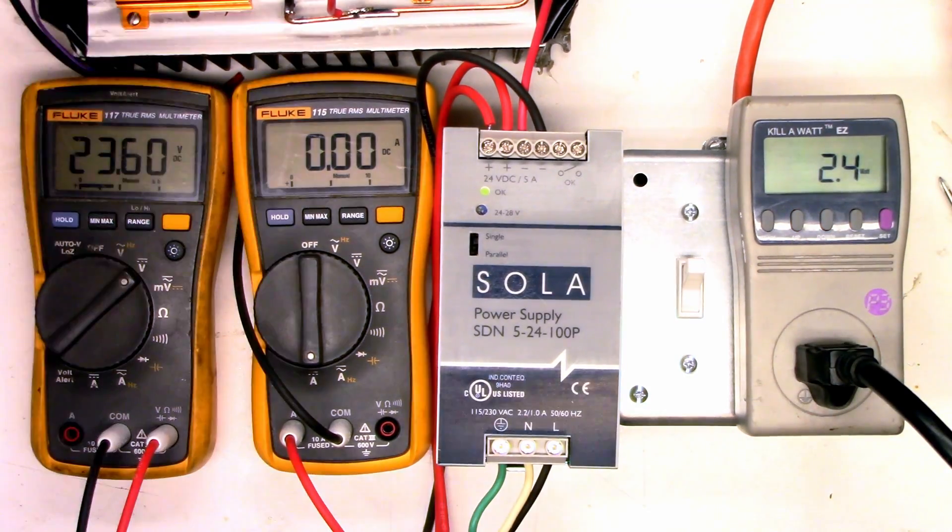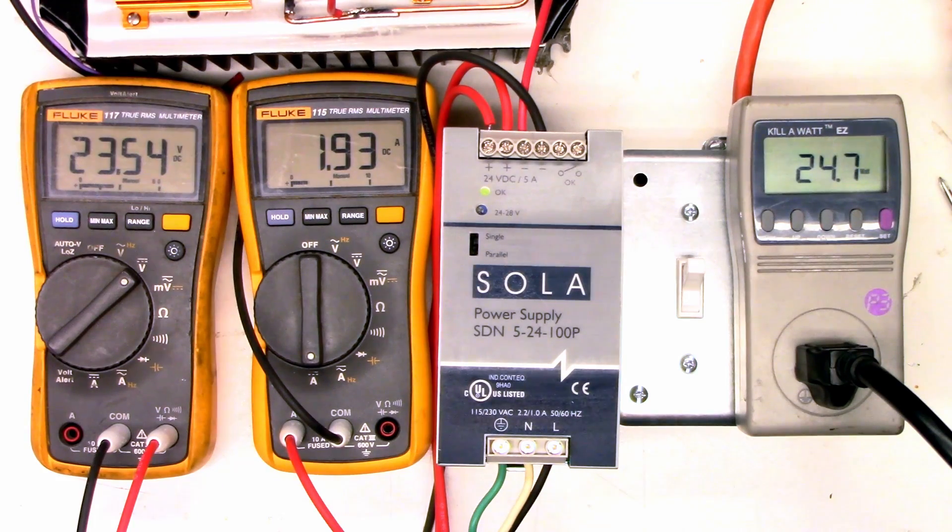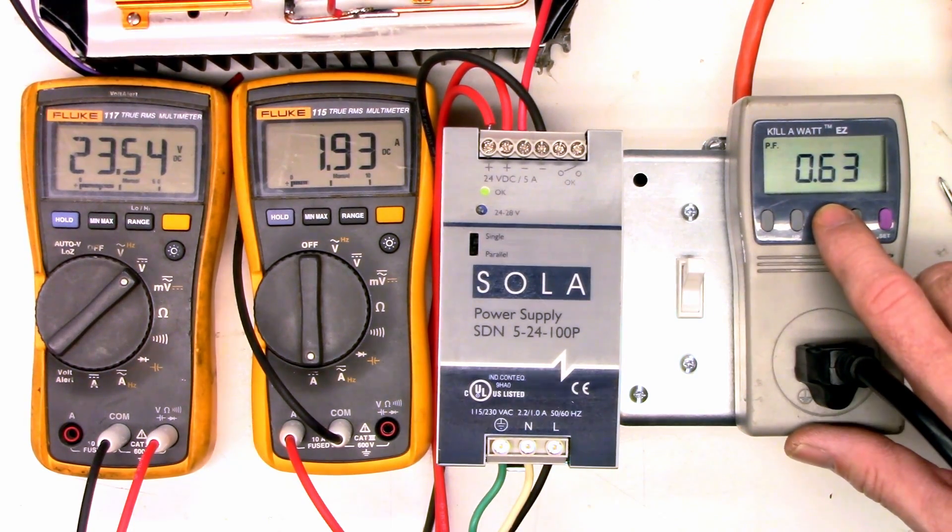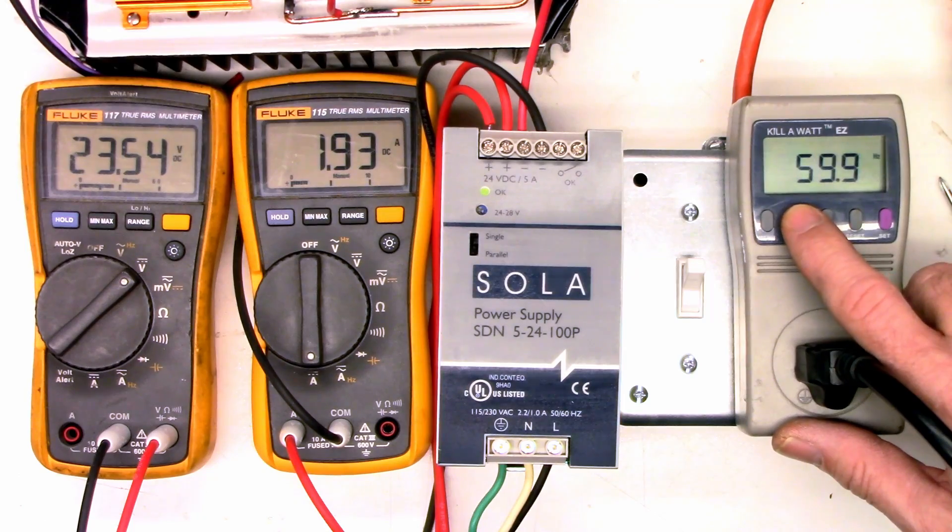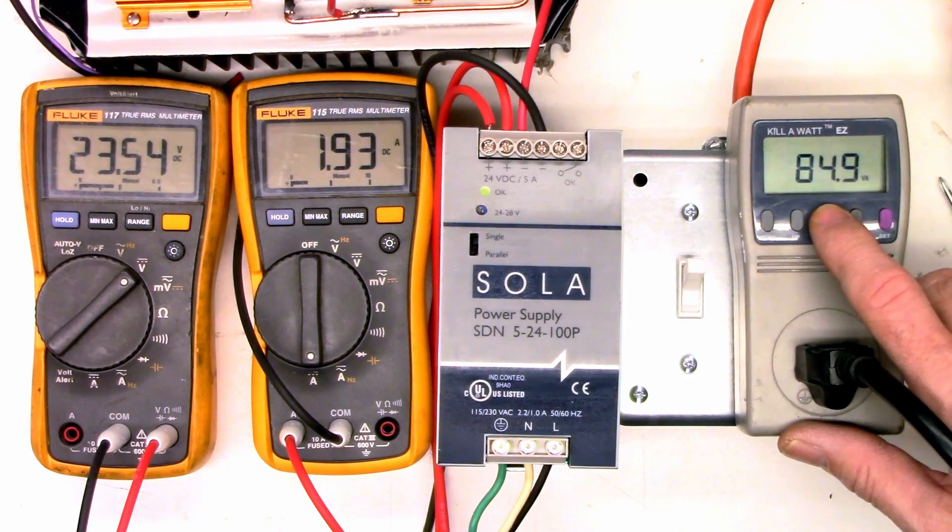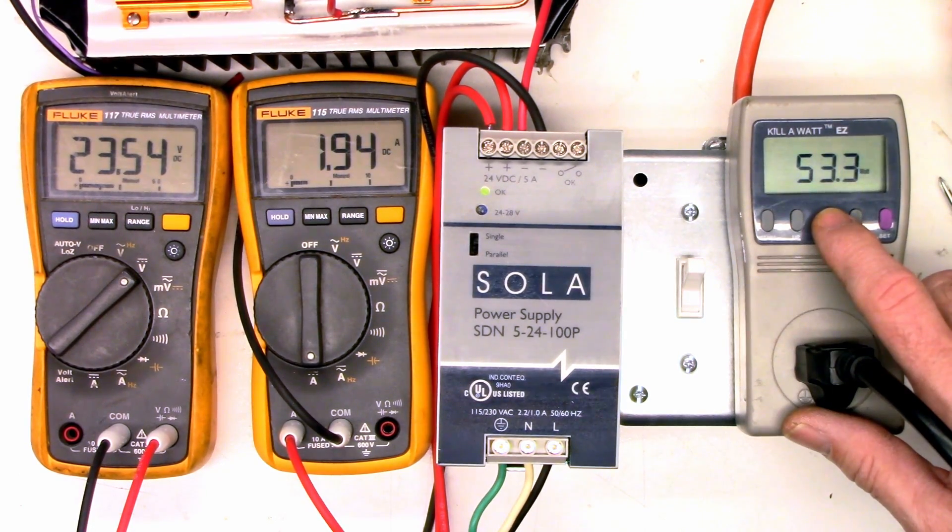Now let's turn on the first load. We have 1.9 amps, and the watts went up to 54 watts. Let's look at the power factor now. The power factor went up to 0.63, 0.64. But look at our VA now. It's only 84, and our watts is 53. That's pretty close now.